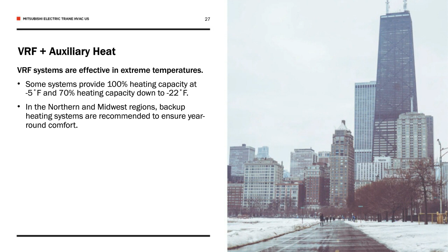Now let's talk about auxiliary heat. Contrary to past perception about heat pumps and variable refrigerant flow technology, these systems actually do extremely well in cold climate applications. As an example, City Multi Hyper Heating units are able to provide 100% of their rated heating capacity at -5 and up to 78% of that rated capacity down to -13 degrees outdoor ambient conditions. That said, for extreme temperatures that are below that threshold or even close to it, and I'm sure many people can remember the past winter's polar vortex in the Midwest, supplemental heat is definitely preferred by designers.